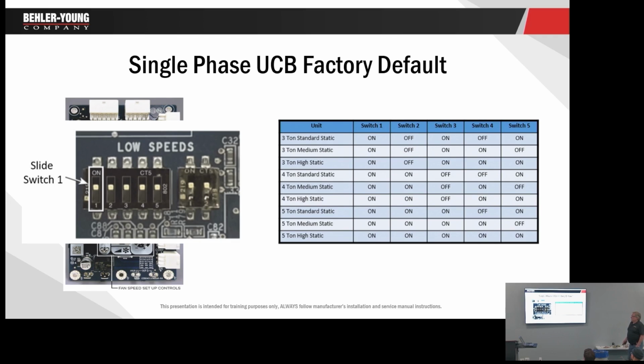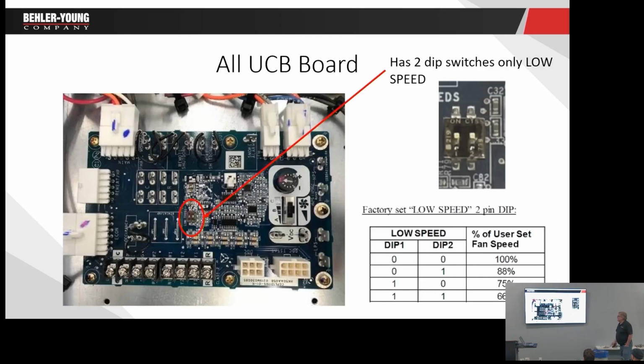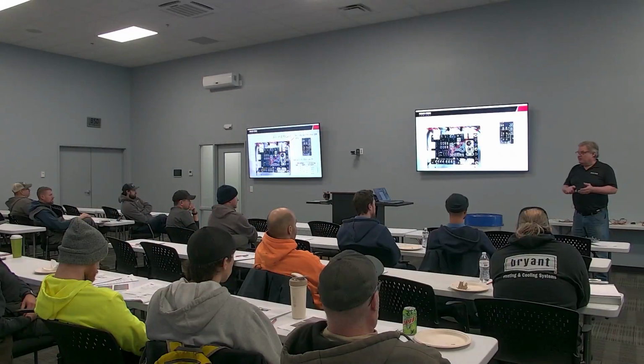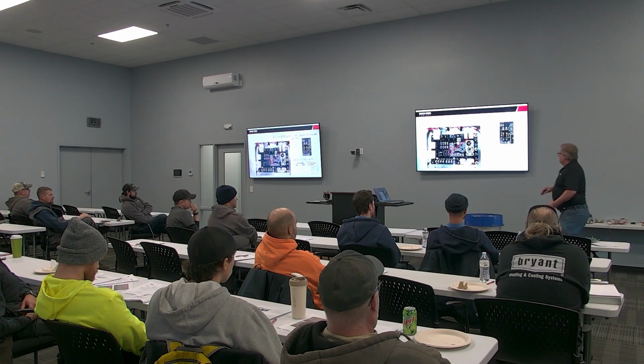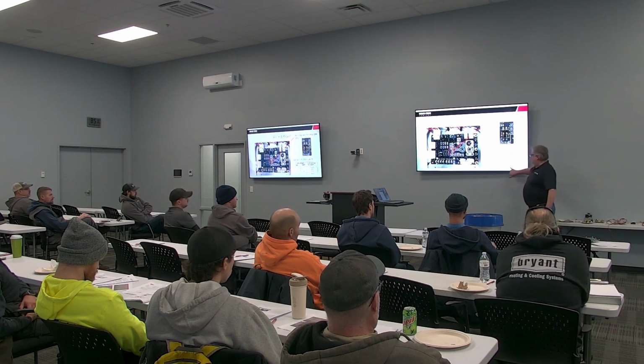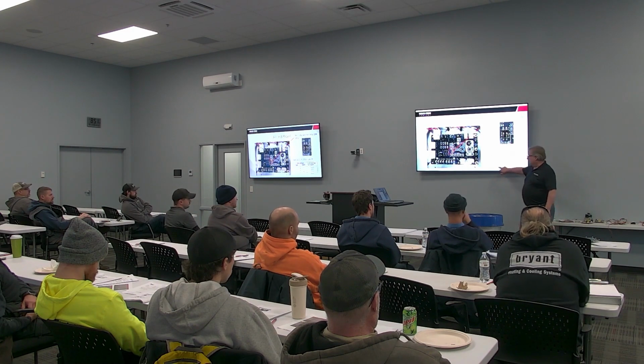All right. Now, it also has this bank of 2 switches here, and the 3-phase has that same bank. Okay. Remember I said that by that ASHRAE standard, we have to have a 2-speed blower? This is going to tell the unit what to do with that blower in low speed, meaning R to G, circulation, or low speed cooling. Okay, out of the factory, it will be set for 66%, so both switches will be turned on.